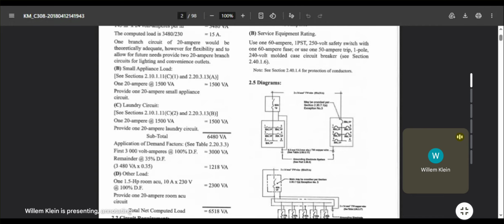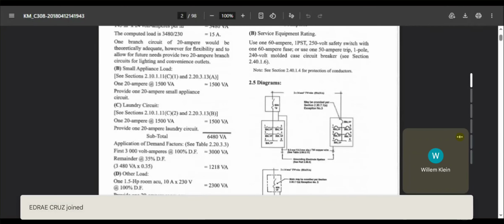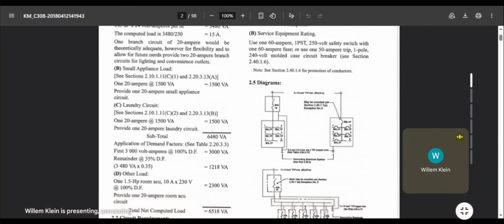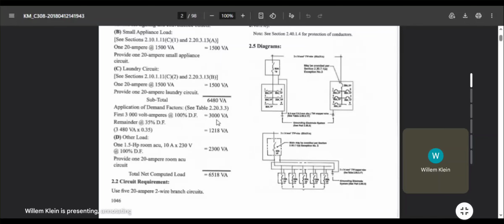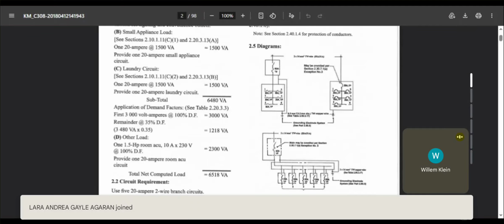Okay? So, first 3,000, 100% demand factor. It means that those amount of load for your circuit gets utilized the most or continuously. So they are the ones that you will always utilize at 100%. While the excess, for example in this one, the excess 3,480 VA, you will only use 35% demand factor for the next up to 120,000 VA or 120 kVA. Because that amount of load will not always be utilized on a day-to-day basis. So that is for a residential.